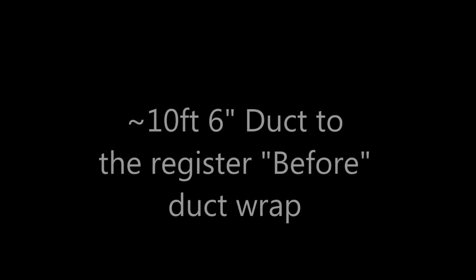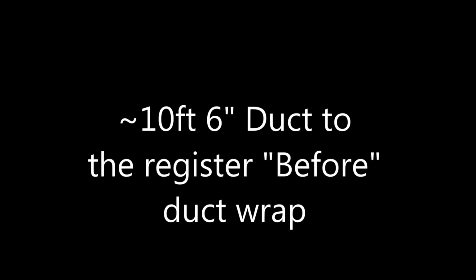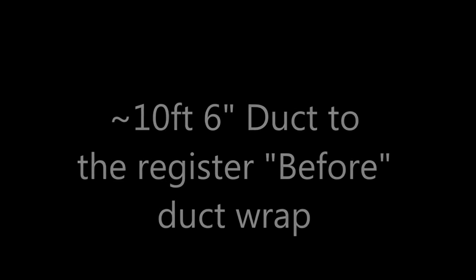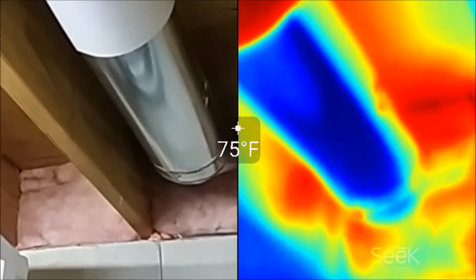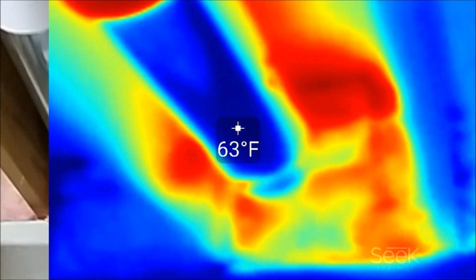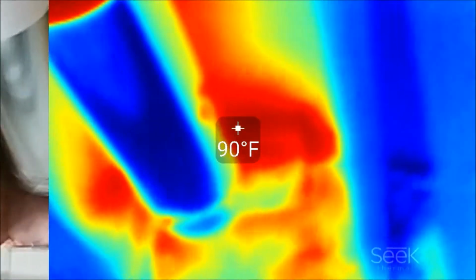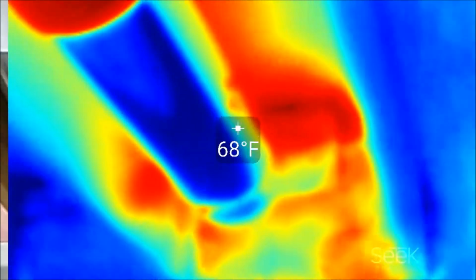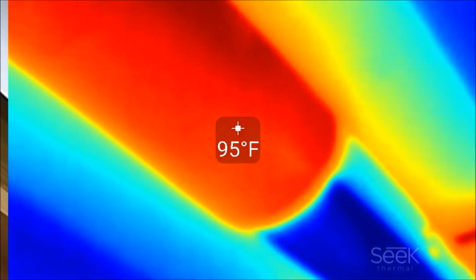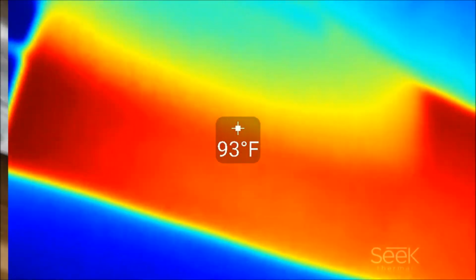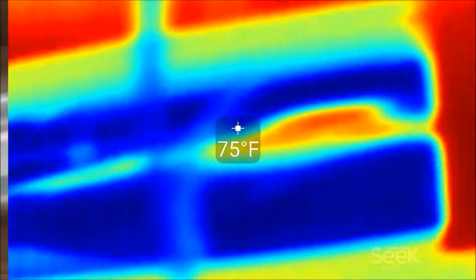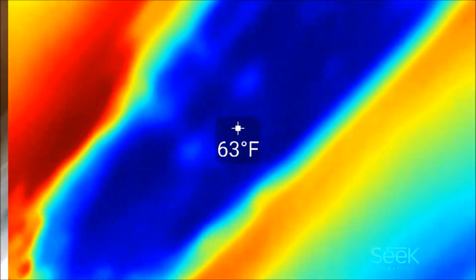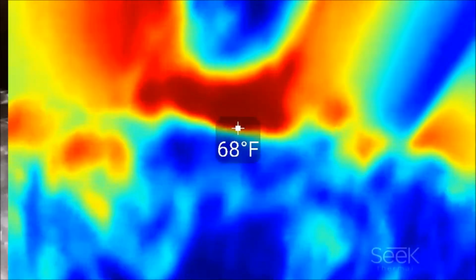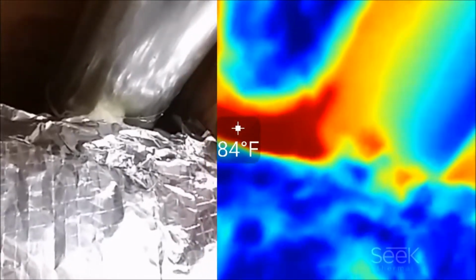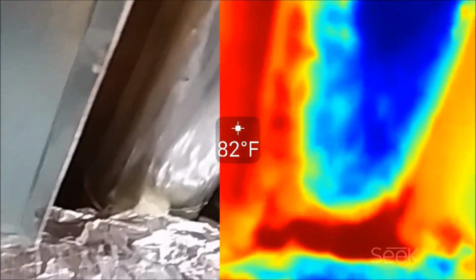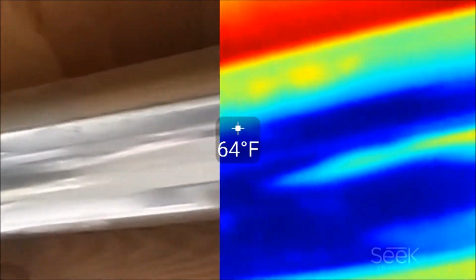Okay, the next thermal imager shot will be underneath the register, the ductwork that's going to the register I just measured. So here you can see I taped a piece of paper to the top of the ductwork because the thermal imager does not respond well to metal. So this is the way to allow the temperature still to be taken. And so you can see it's about 95 degrees on the pipe itself. And back at the supply plenum it's kind of heated up there. So you can see it's definitely hot inside that cavity.